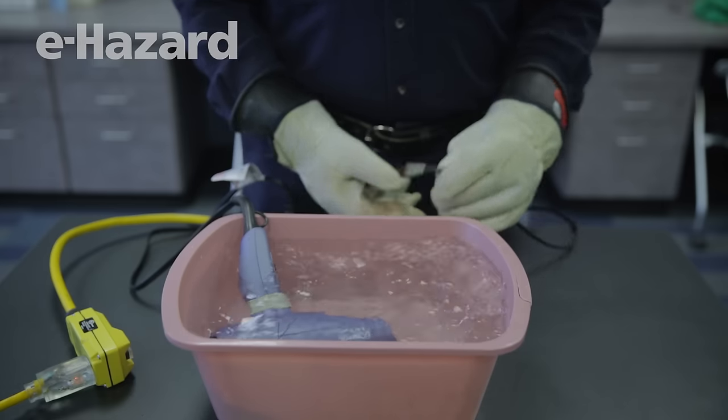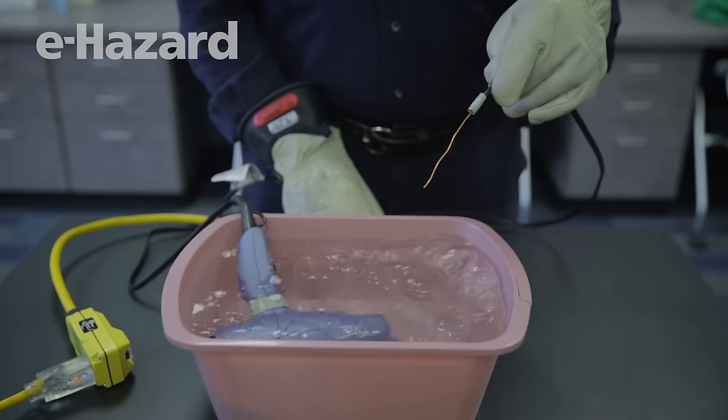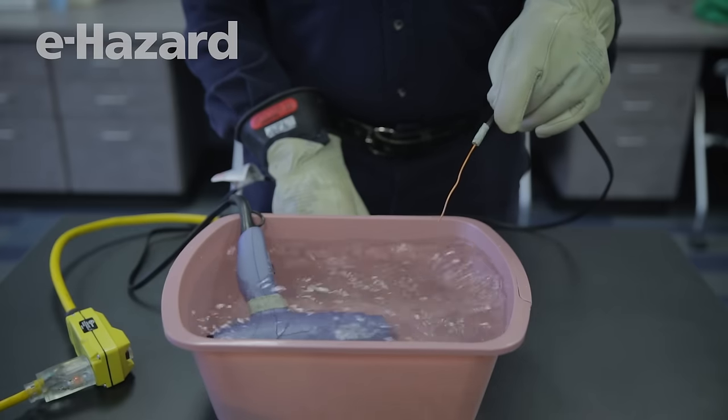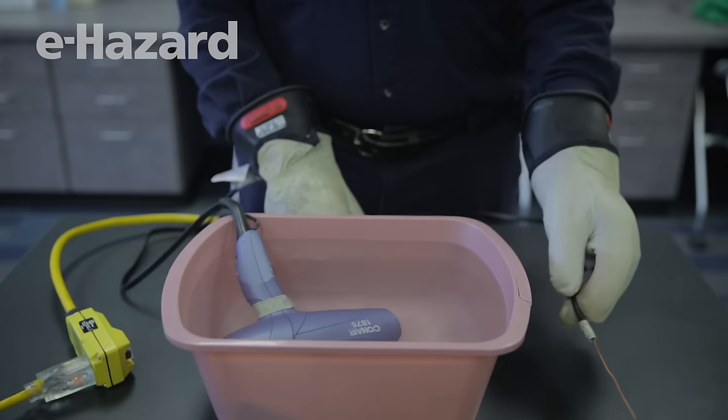So watch what happens when I take the ground rod. I can put it anywhere in this water, and as soon as I establish a ground, the current's going to flow through this ground rod back to the GFI, and it should trip. Now at this point, the power's taken off.